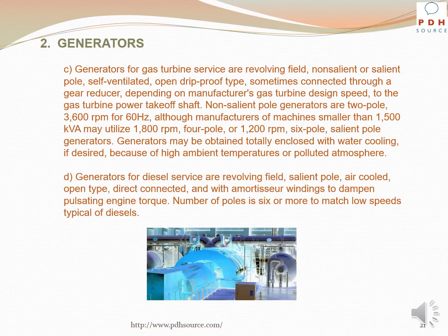Generators for gas turbine service are revolving field, non-salient or salient pole, self-ventilated, open drip-proof type, sometimes connected through a gear reducer depending on manufacturer's gas turbine design speed, to the gas turbine power takeoff shaft. Non-salient pole generators are 2-pole, 3600 RPM for 60 Hz, although manufacturers of machines smaller than 1500 kVA may utilize 1800 RPM 4-pole or 1200 RPM 6-pole salient pole generators. Generators may be obtained totally enclosed with water cooling if desired because of high ambient temperatures or polluted atmosphere.